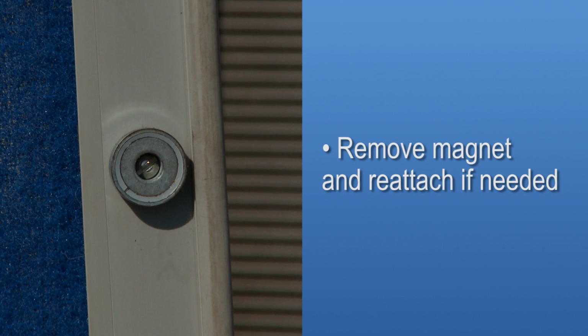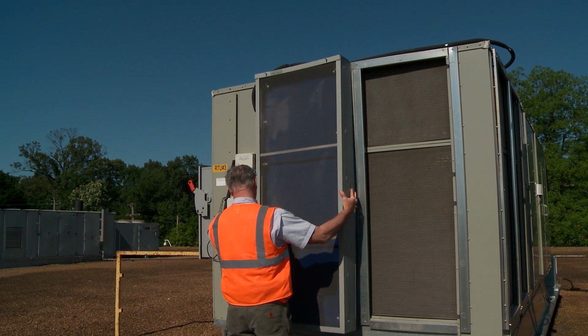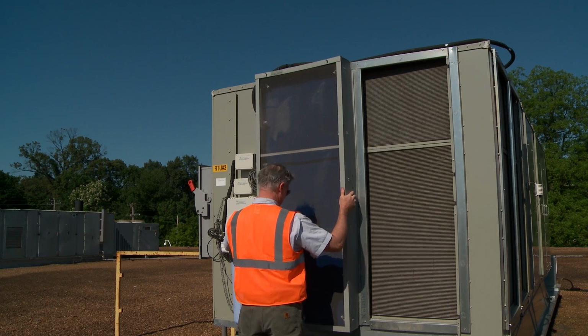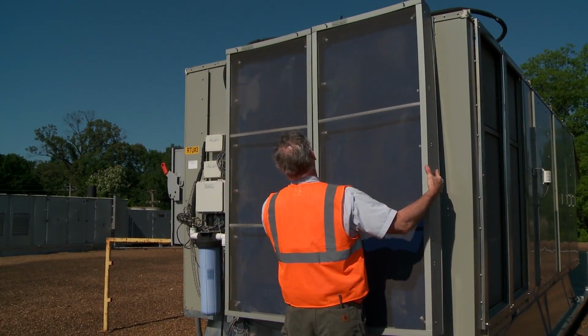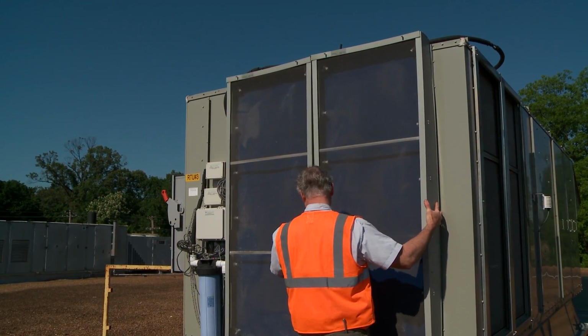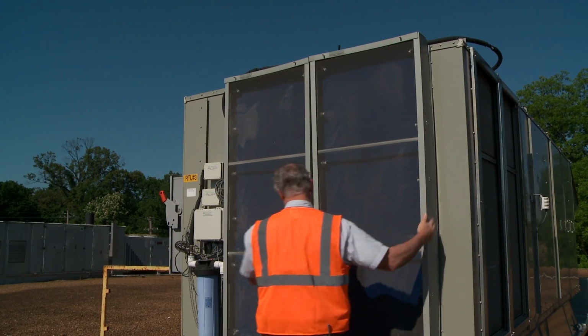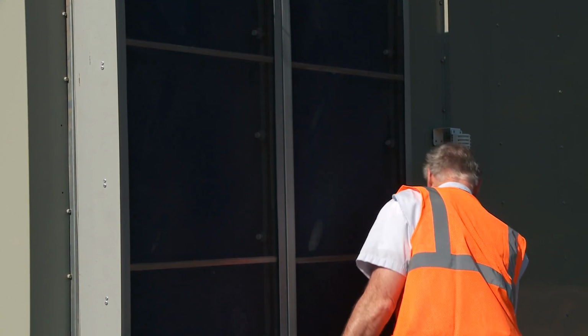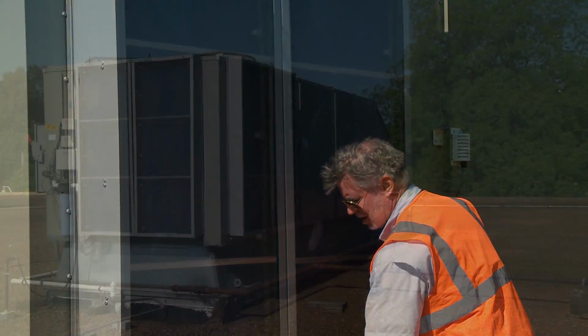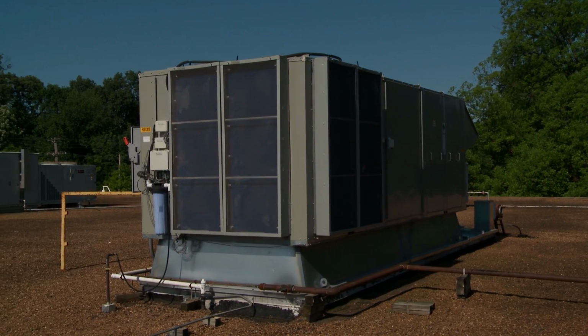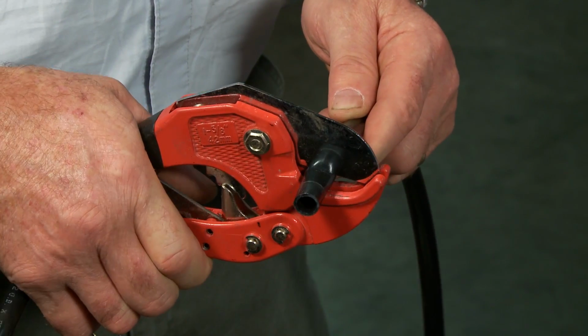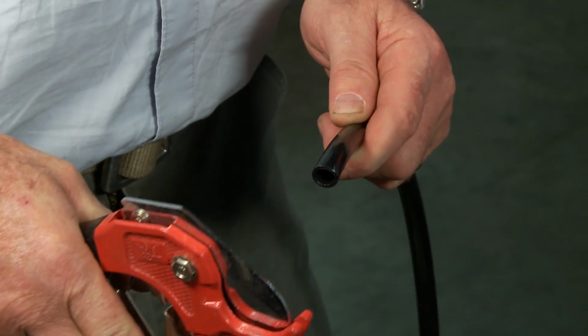Although not anticipated, in the event a frame magnet hits an obstruction on the condenser unit like a screw head, remove the magnet from the frame and reattach it to a location free from the obstruction. A completely sealed, flat installation is necessary for proper airflow through the easy frames. The installer is responsible for ensuring that this is the case. Once all frames are secured to the unit and any gaps behind the frames properly covered or closed off, the included flexible tubing can be measured and cut to length.